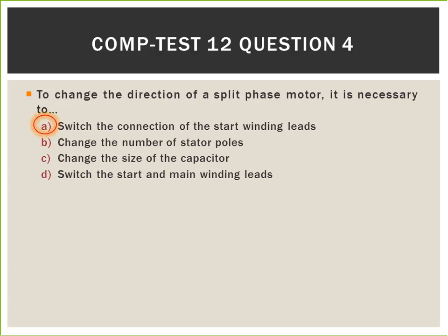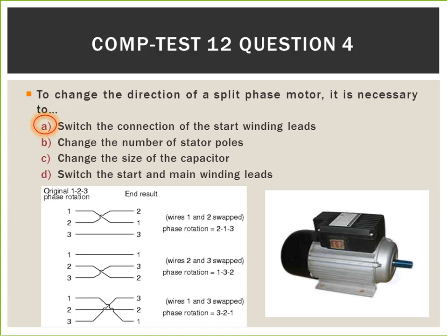Answer A is the best answer here. As seen in the photo on the left, no matter which two starting winding leads are swapped, it ultimately reverses the phase rotation and changes the direction of the split-phase motor.